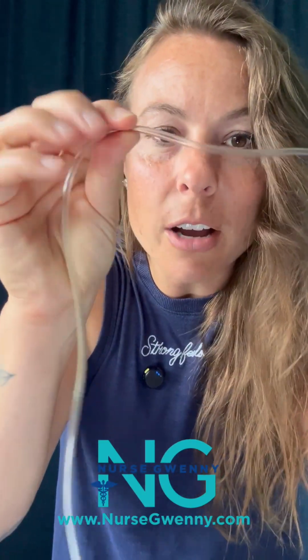Right here in the middle, we have the transducer. Everything branches off from this. We have our cable that hooks up to our monitor. We've got the soft tubing. See, this is nice and soft and flexible. This goes to our bag of fluids. It's going to be at 300 millimeters of mercury. And then this other part, this rigid tubing that you're not able to kink off or pinch, is going to connect to the patient's usually radial artery. So it's going to go right here on the patient.